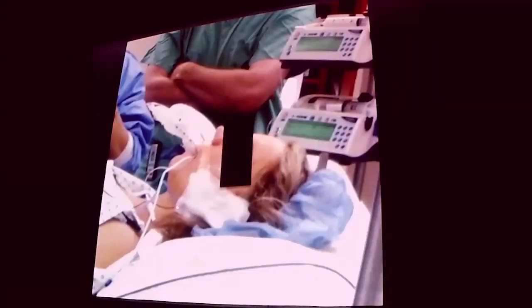Setup is key to BAERs. Because you all know there's the tubes, there's the ear inserts. You've got to keep them safe. And as you can see, I'm a fan of tape. This keeps everything in the ear. Now you have to be aware that if you're going to do a posterior fossa, you don't want the tape to get in the way, because what happens? The surgeon comes and rips it off, and when he rips off the tape on the ear, everything you have in the ear comes out of the ear.